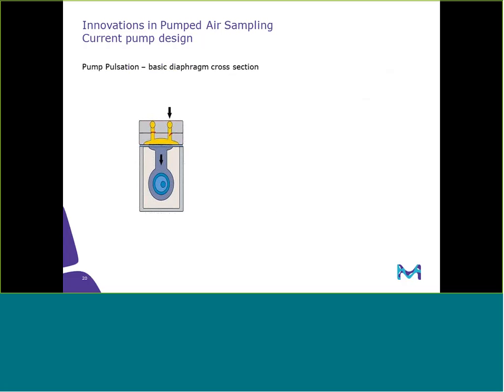We'll move on to current pump designs. Today's pumps are based off a diaphragm pump. Pretty simple. This is a basic cross-section of how a pump diaphragm would work. Diaphragm pumps contain a chamber, plunger, or a piston, and as the motor turns, the diaphragm oscillates back and forth, which creates a vacuum and pressurizes the pump chamber.